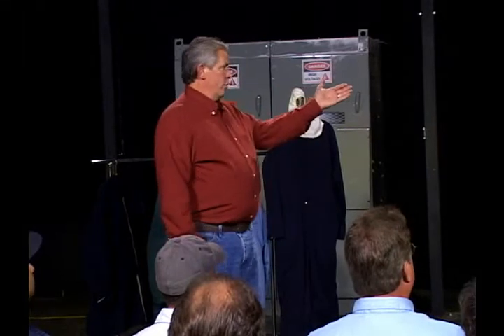Some arc facts you might not be aware of: over 80% of all electrical injuries are due to ignition or flash burns, arc flash, and ignition of flammable clothing like cotton. Now I know you've probably heard, oh just wear 100% cotton, that's all electricians have to do. 100% cotton is not adequate. It's only good for category 0, which is minimum job task and minimum energy levels.